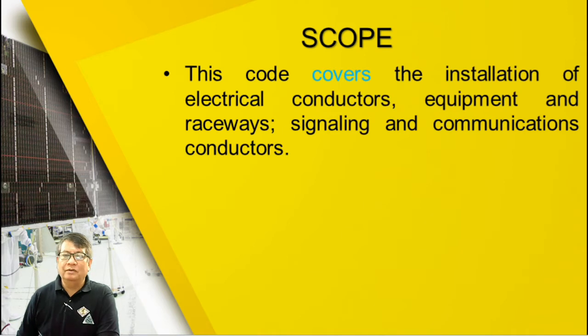So we have this scope of the Philippine Electrical Code. This covers the installation of electrical conductors and equipment: the conductors, you have the wire, the cable, and the equipment, and raceways. A raceway is used to protect our conductor, the insulation. So we have what we call tubing or raceway here. Signaling and communicating conductors. When we say signaling, this is basically used for sensors, for maybe fire, fire suppression, control and protection. And then the communication system, cabling for the internet or any internet connections, cabling and networking.